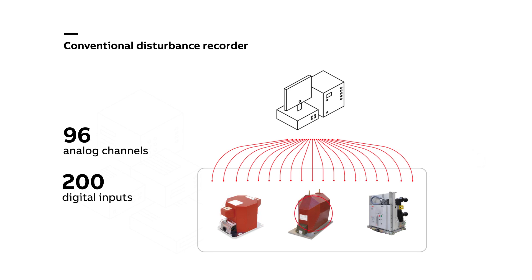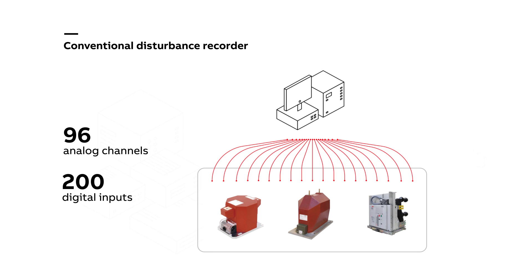Buchholz relay and similar—all these need to be hardwired to a freestanding panel because a conventional disturbance recorder is so large that it cannot be inside the medium voltage switchgear panel itself. This separate freestanding panel houses cooling and other auxiliary devices.